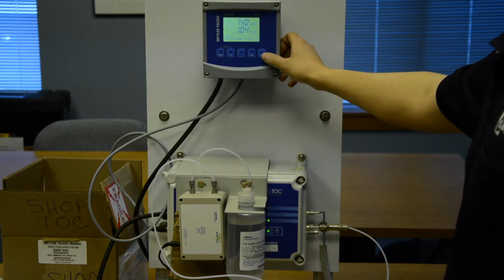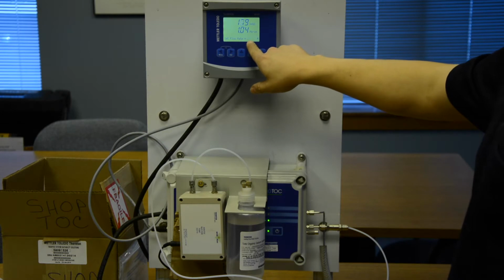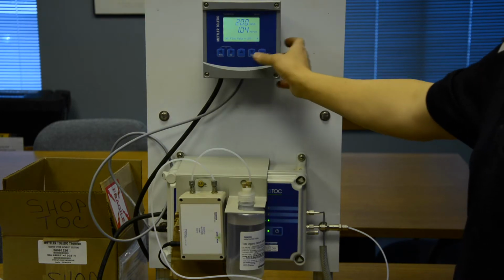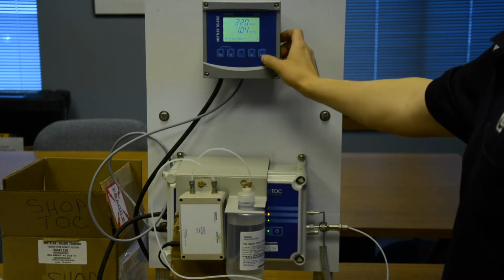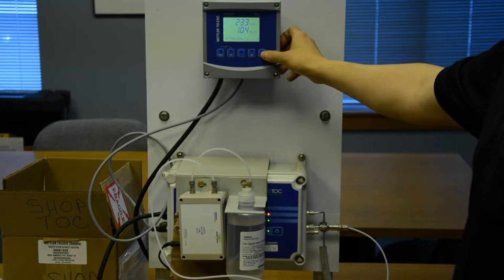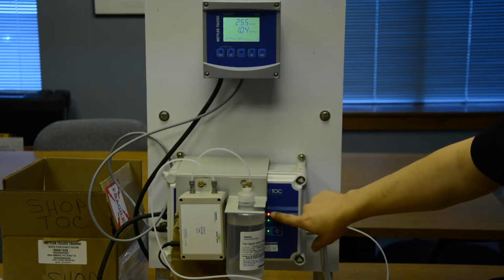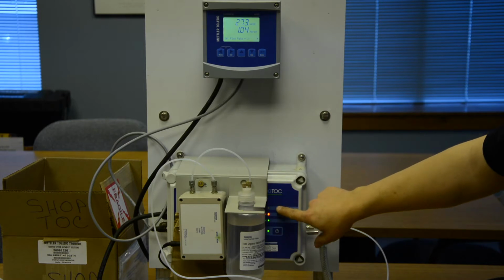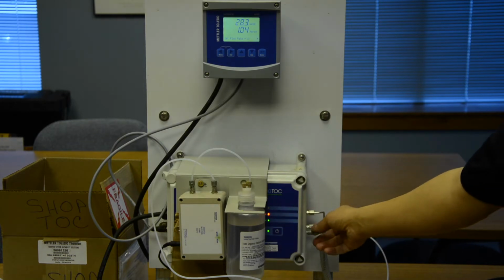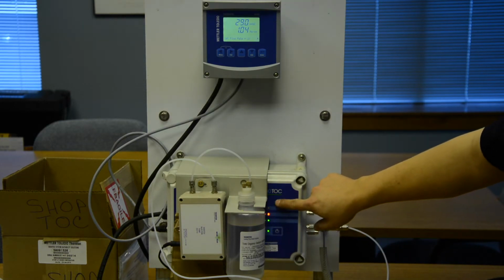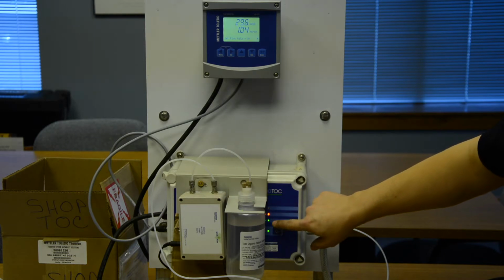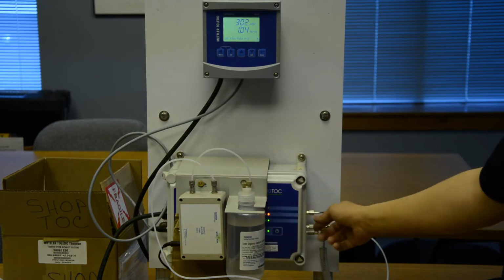Hit enter. It says set flow rate, and off is flashing. Press the up arrow. It'll say on, hit enter. When you do this, you'll see lights that will appear on your 4,000 or 5,000 TOC unit. These lights indicate the level of flow. At 20 milliliters of flow, all 4 lights should be lit.